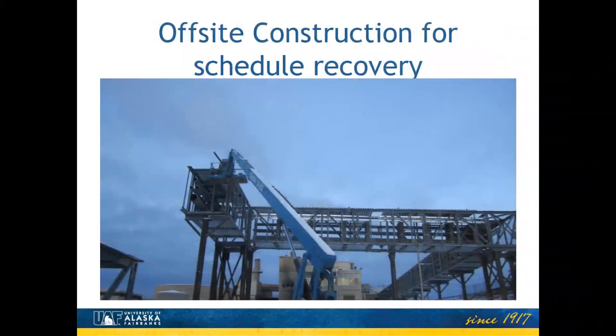Some of the other things we did to accelerate the schedule were fabricate some pieces off-site. One of the most notable features of that is this pipe bridge that connects the Atkinson building to the new power plant. It's real visible from Alumni Drive and stands out when you look at photos of the plant. And that we had fabricated offsite into sections that were all between 30 and 40 feet long, had the pipe and cable tray loaded in it. And then we did the piles that support it ahead of time. And when these arrived, it took just 6 days to run that 440 feet of building and tie it together. And so that helped us maintain our schedule also.